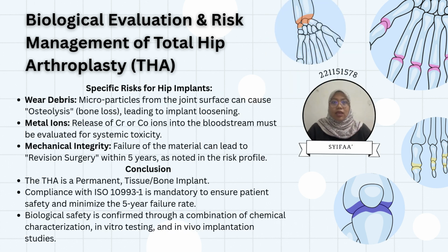Beyond basic toxicity, we must address three specific clinical risks. First is wear debris. These microparticles can trigger osteolysis, where the body absorbs its own bone, causing the implant to loosen. Second is metal ion release. We must ensure that ions like chromium and cobalt don't reach toxic levels in the bloodstream. Finally, we monitor mechanical integrity. If the material degrades or wears too quickly, it leads to revision surgery within that critical 5 years window. Our goal is to ensure the biological response doesn't compromise the mechanical fix.